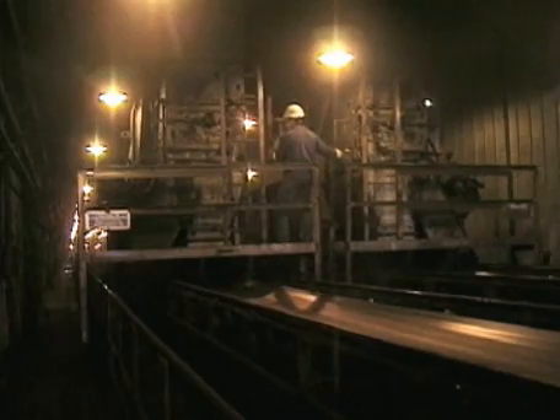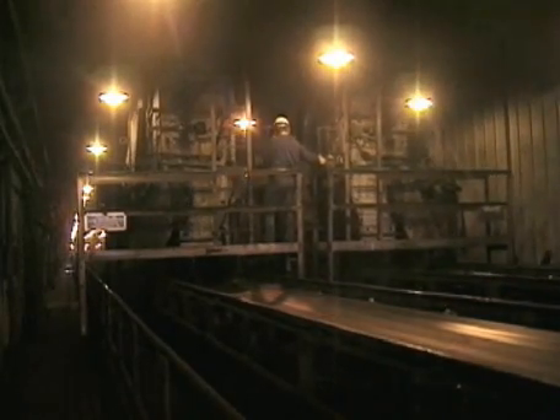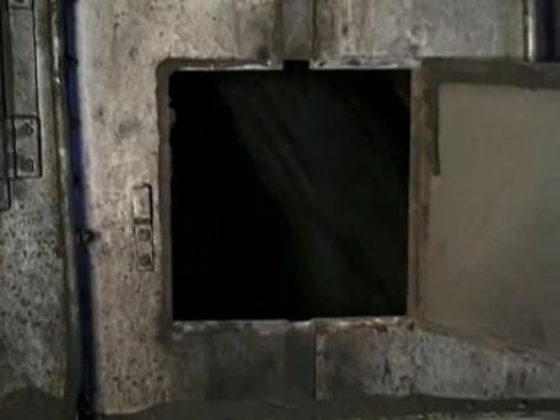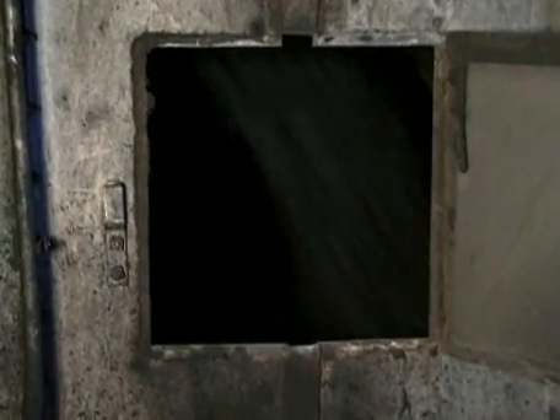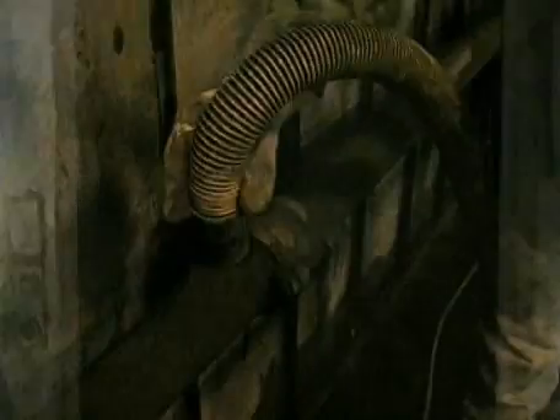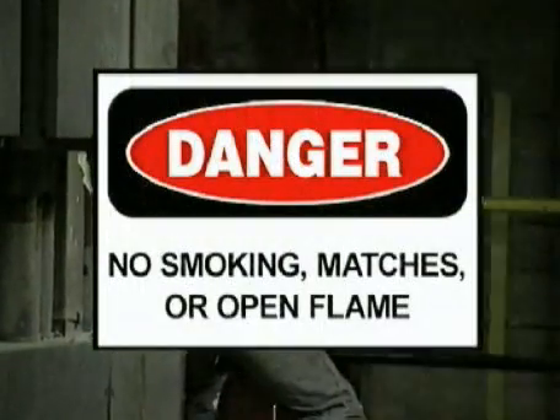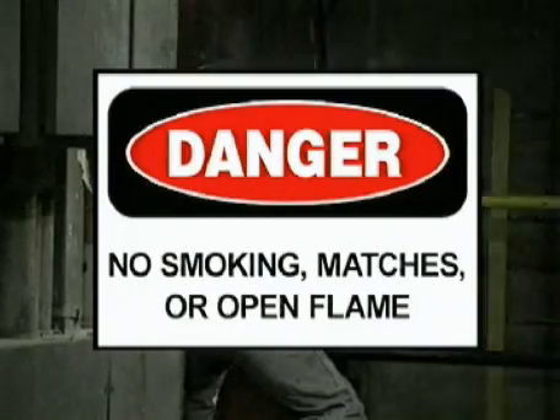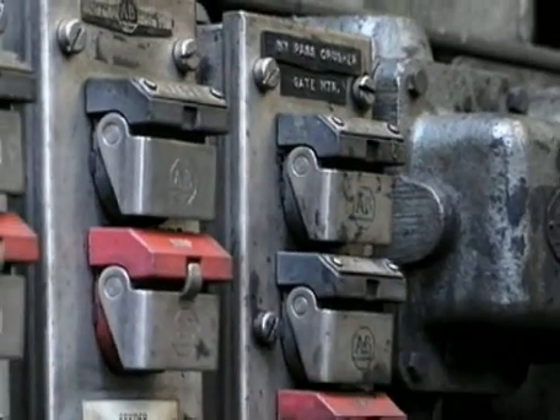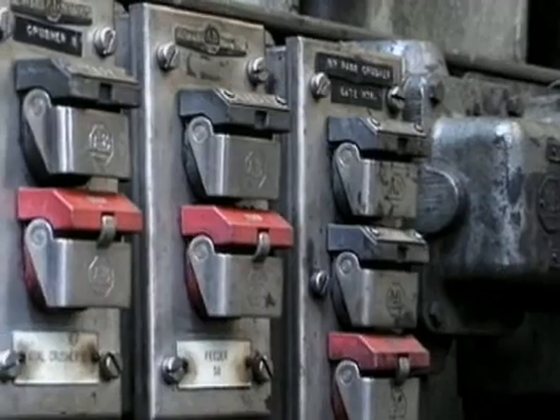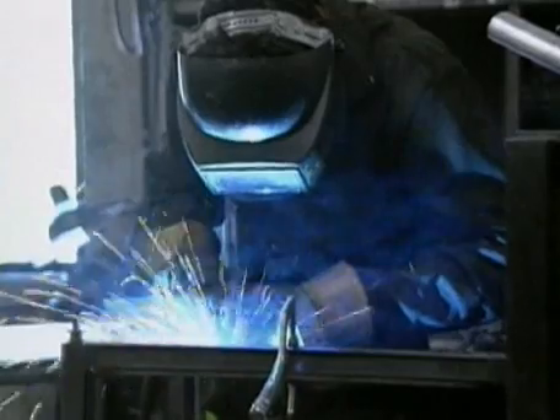While working at PPL, your job may be performed in certain areas containing coal dust. This dust is created in the coal handling process and can pose a significant threat if not properly managed. In addition to the use of respiratory protection, other precautions must be taken. Smoking and open flames are not permitted in areas subject to coal dust. Electrical equipment must be classified for use in hazardous dust environments. Dust ignition-proof devices are also required. You should follow OSHA standards with respect to operations that involve brazing, cutting, and welding.